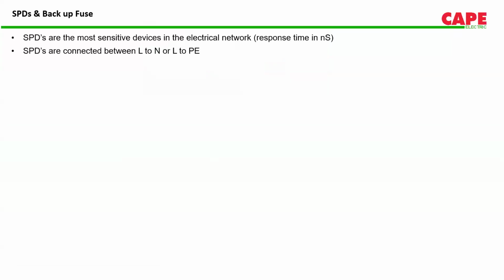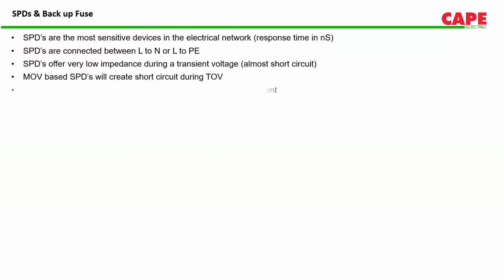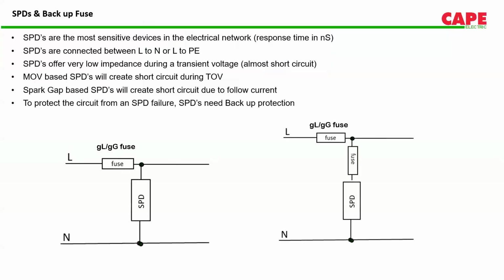SPDs are the most sensitive devices in an electrical network. They have a response time in nanoseconds. Mostly SPDs are connected between line and neutral or line and earth, depending on the connection type, 3 plus 1 or 4 plus 0. Normally, there are two kinds of major components used inside an SPD. Either it's an MOV or a spark gap, or it can be a GD tube also. In the case of an MOV, during TOV conditions, temporary overvoltage conditions, it may fail and create a short circuit. Similarly, spark gap SPDs may create a short circuit due to follow current. So I'll just show you.